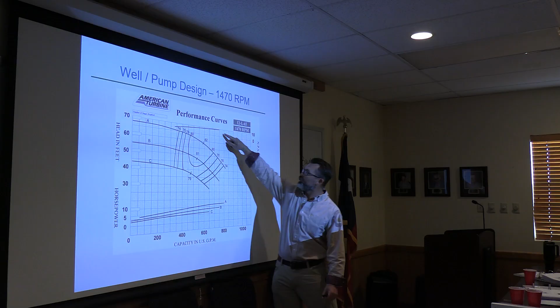Then what you've got in the middle here are these efficiency curves. Okay, so in this case, like an 82% efficiency and 81% efficiency, this loop would basically be the 80%, 78, 76, 74, etc. So the question you'd had earlier is, why do I see some pumps where one has me 86% efficient and the other one has me 82% efficient, but then I come out here to the horsepower side and it's calling for more horsepower on the one that's doing less work?